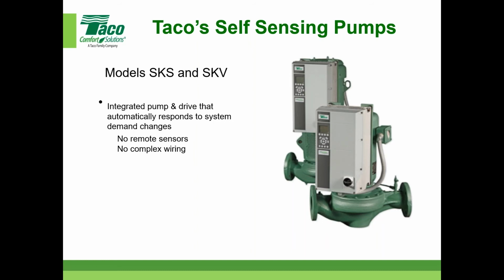Us pump manufacturers have had to do a lot of testing for these models with that drive mounted to it in order to do the lookup tables. It's hard to understand all the details, but there's a lot of intelligence in those drives. And those drives you're looking at are Danfoss drives, and our two main competitors use Danfoss drives as well, because that's the drive company that has the brains to be able to do this stuff.